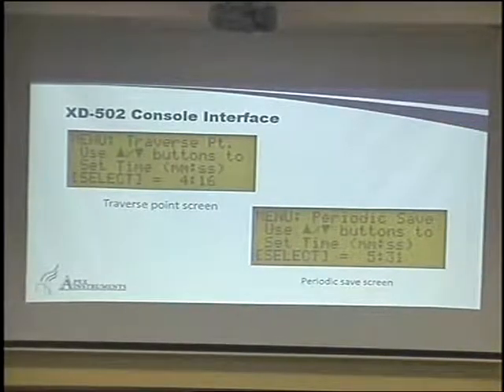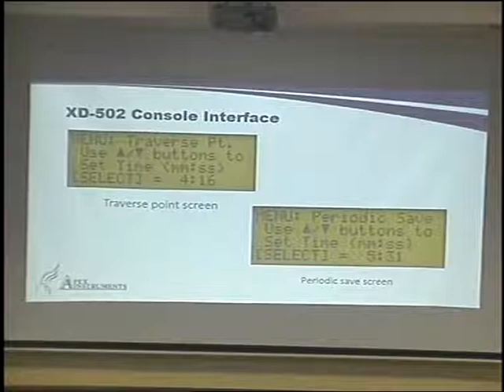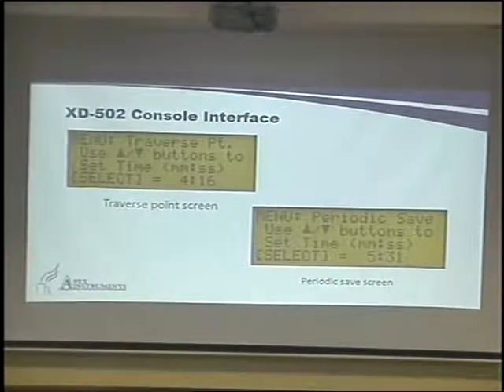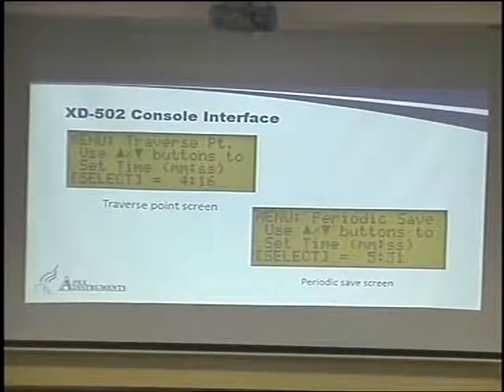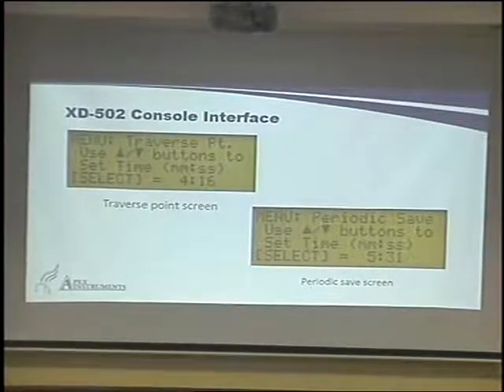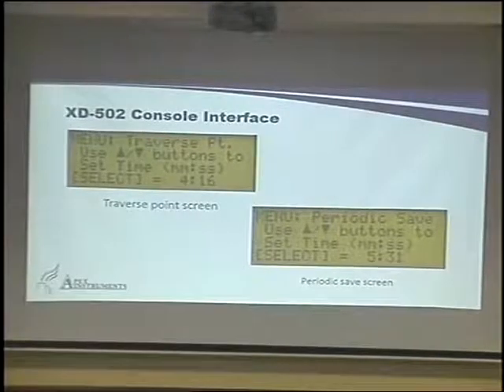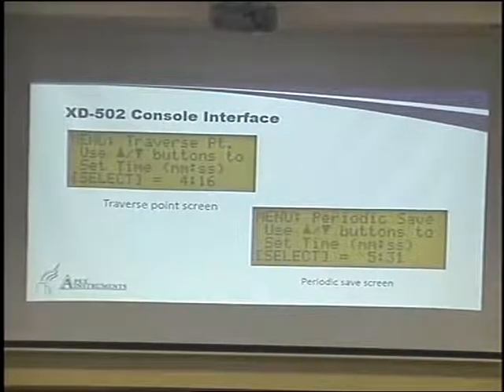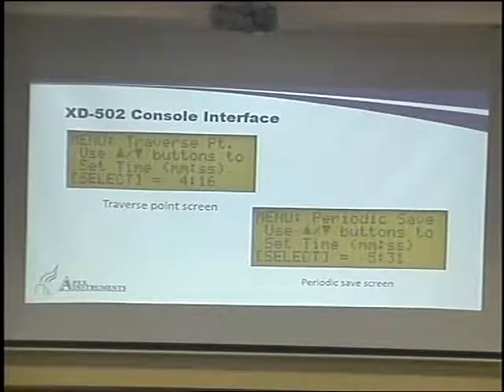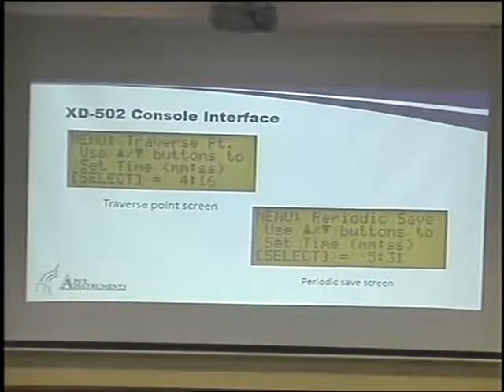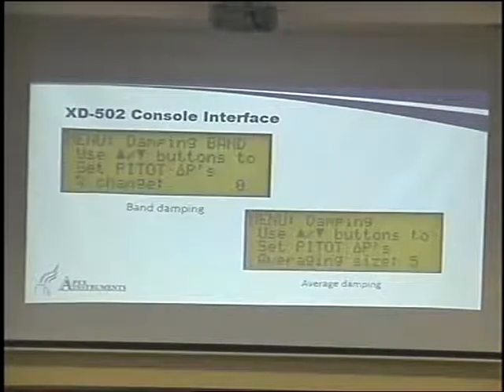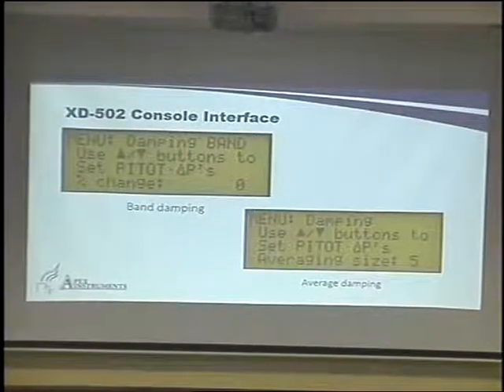And then we can also set a periodic save. So we can say, regardless of the conditions, regardless of where I am in my test, every minute collect all of the data that's coming. Just the raw data. Take a snapshot every minute, every 30 seconds, every 5 minutes, whatever you wish as the operator. So you can take 3 sets of data. You can take the traverse averages. You can take periodic raw data snapshots at whatever intervals you determine you want it to see. And then finally, we can take instantaneous ones by hitting a button.